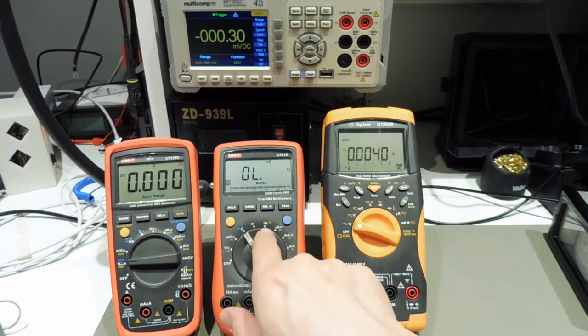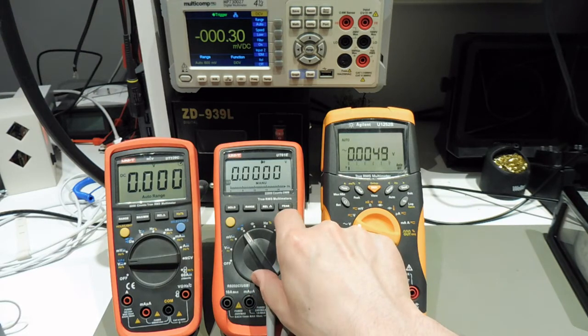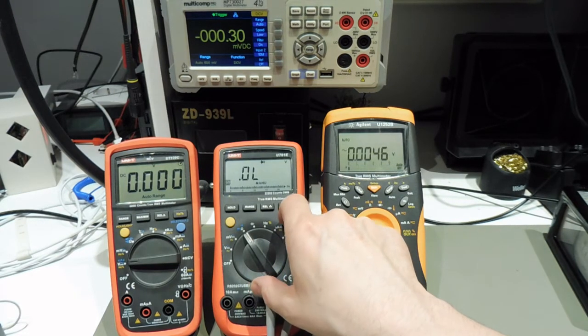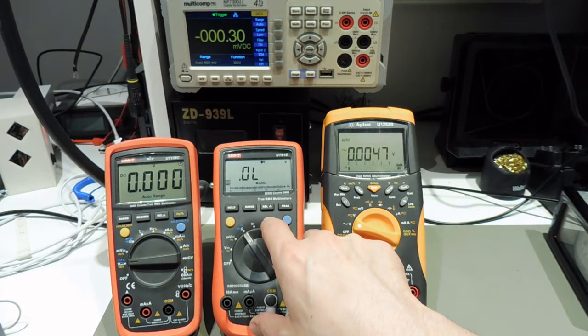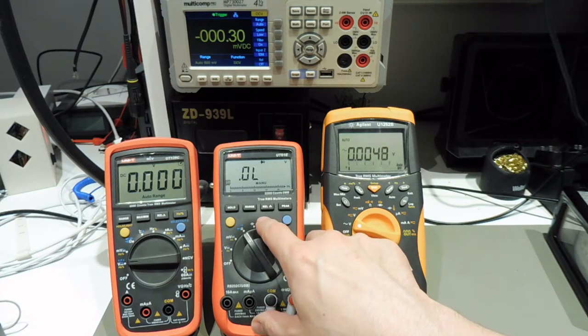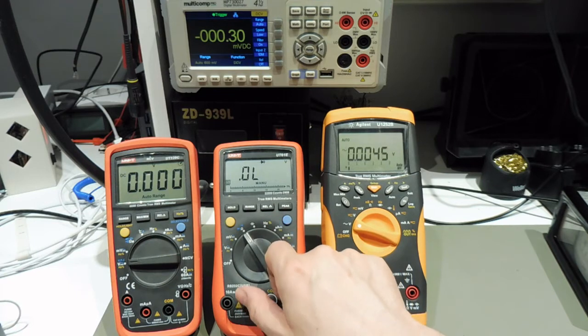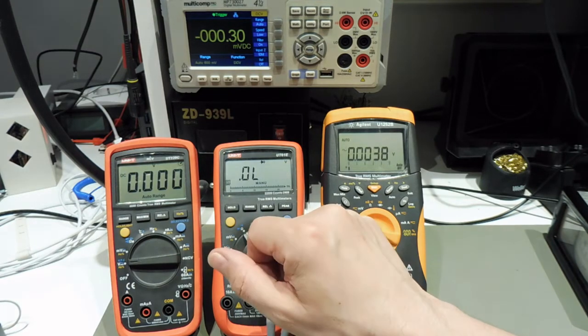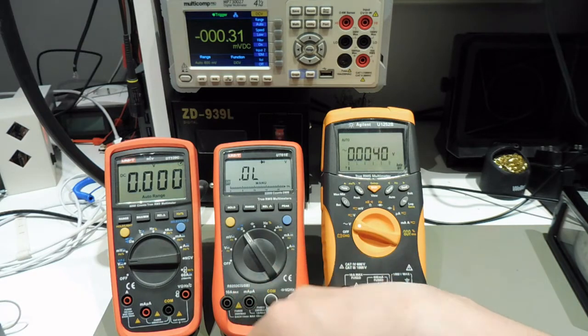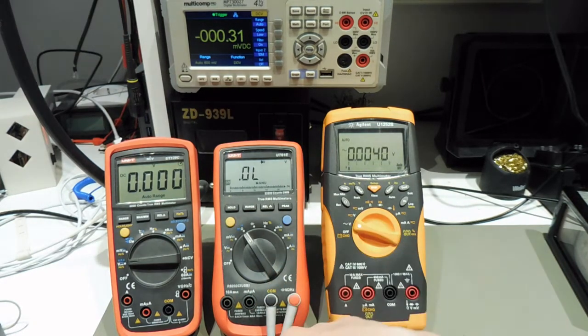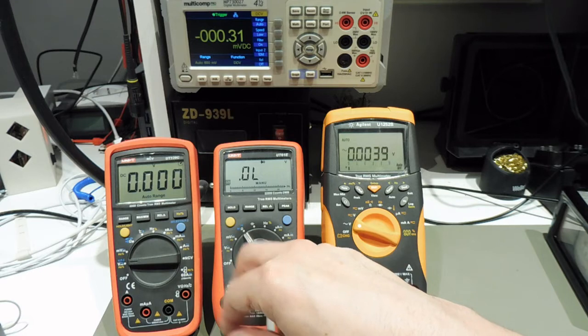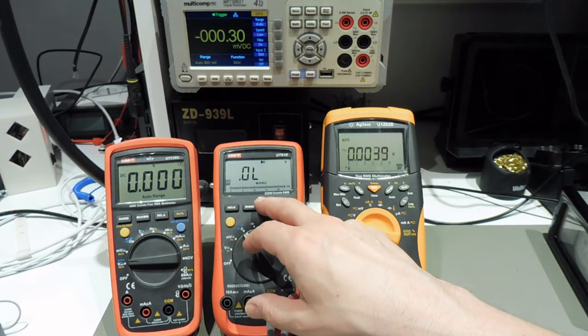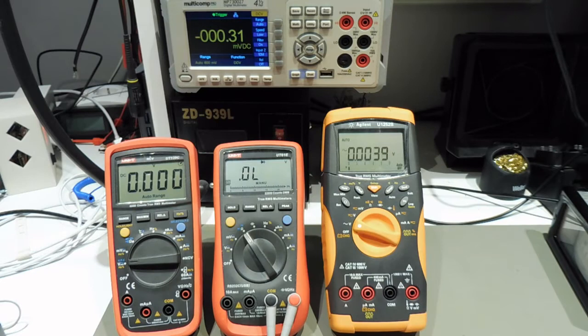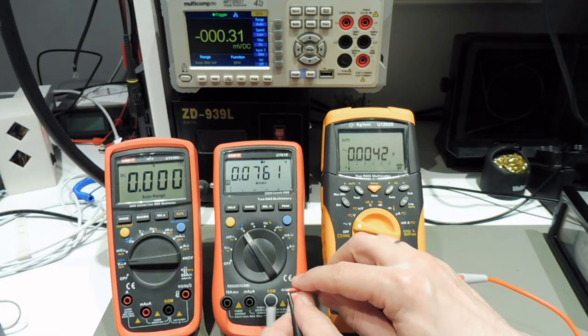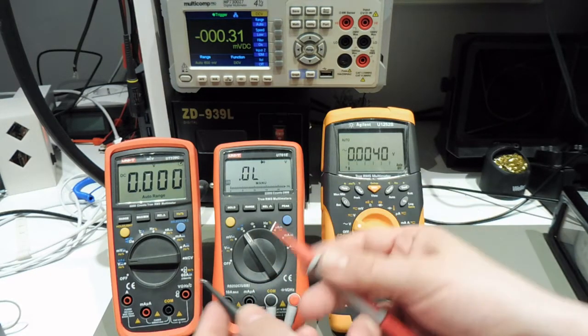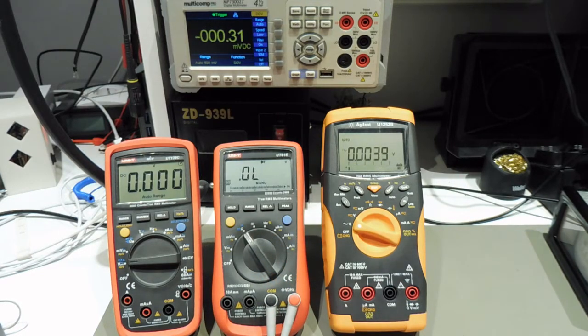Another special range for the resistance mode is usually the diode measurement, which can be used to measure the voltage across a diode. When you want to verify whether a diode is working correctly, you switch to this mode. You'll have a constant current flowing through the diode, similar to resistance, but instead of showing the calculated resistance, you just get the voltage across the diode. If I short this out, you get 0 volts, of course.